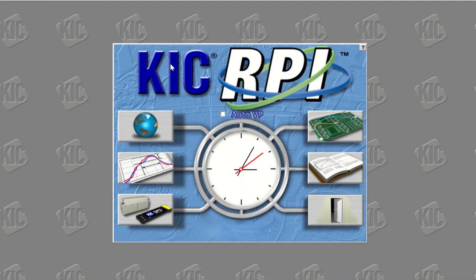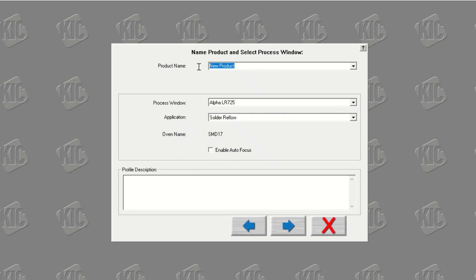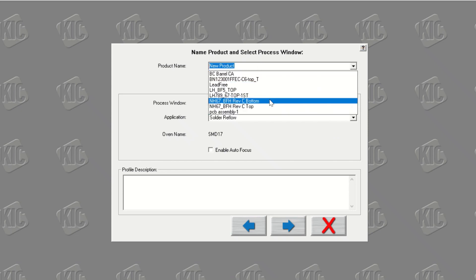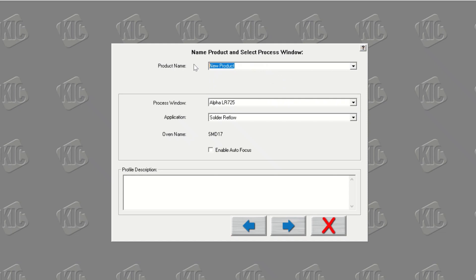Now that we understand the Automatic System's basic concept, it's time to run our baseline profile that we will use as a reference during production. From the main screen, click on the right column top button — the Run a Profile button. In the Product Name menu, you can select any product from the drop-down menu, or you can create a new one if you haven't run a profile for this product before. KIC always recommends that you give the same product name as the oven recipe. This will help the operator to select the same recipe in KIC software and in the oven during production.